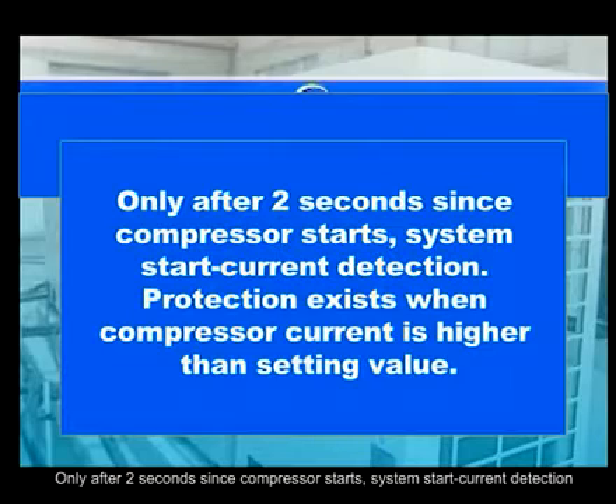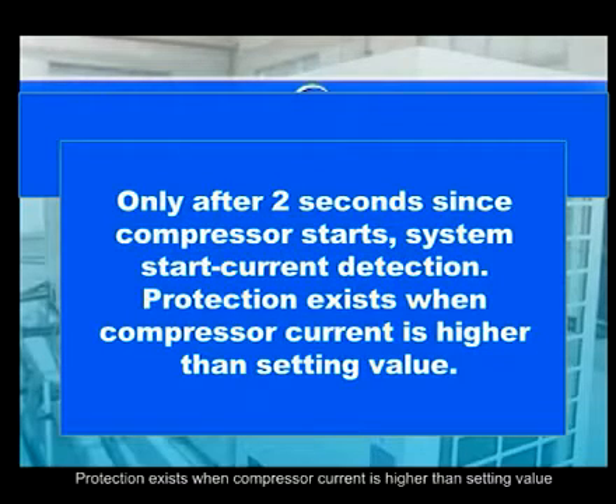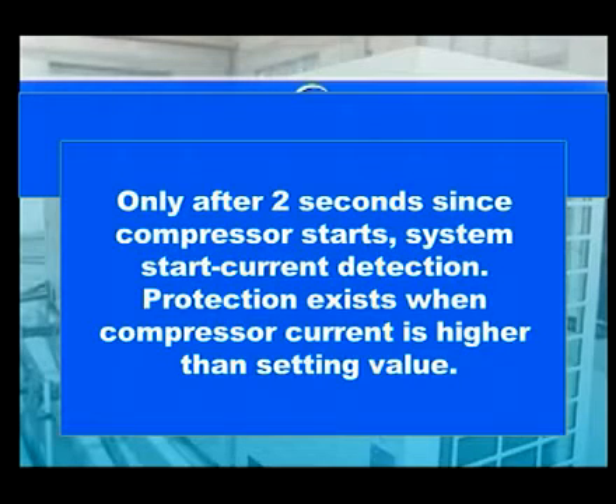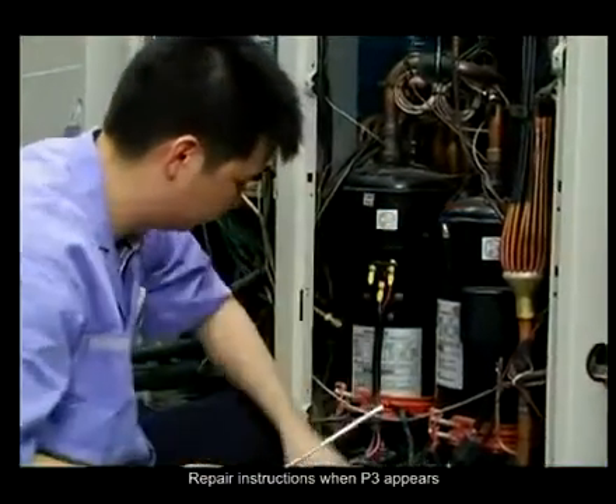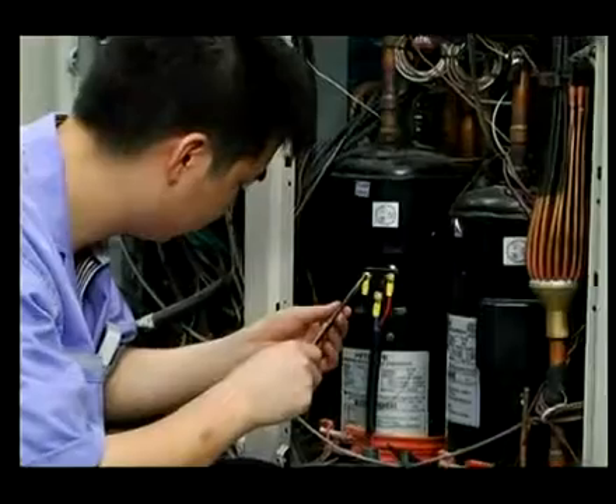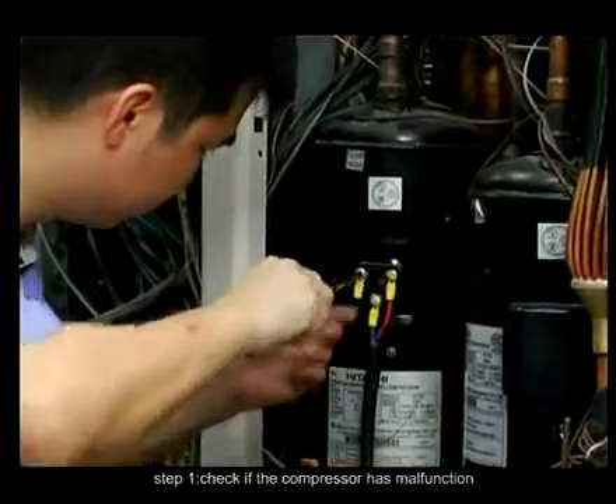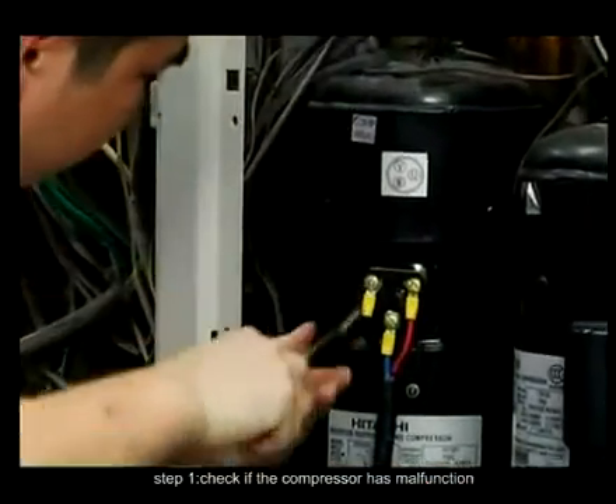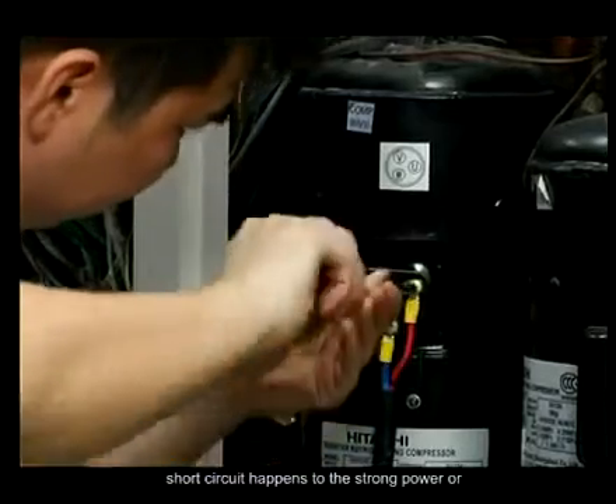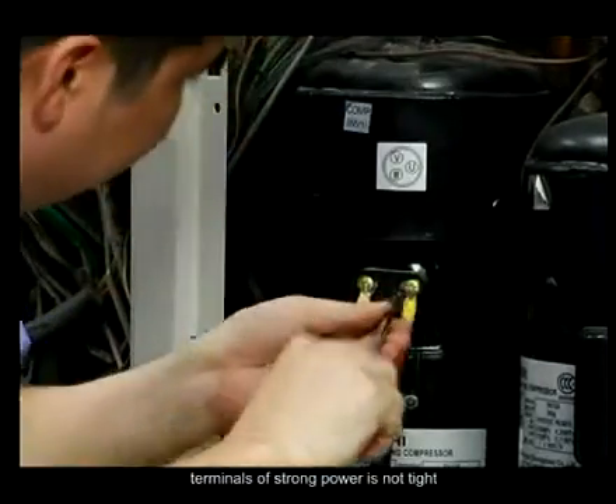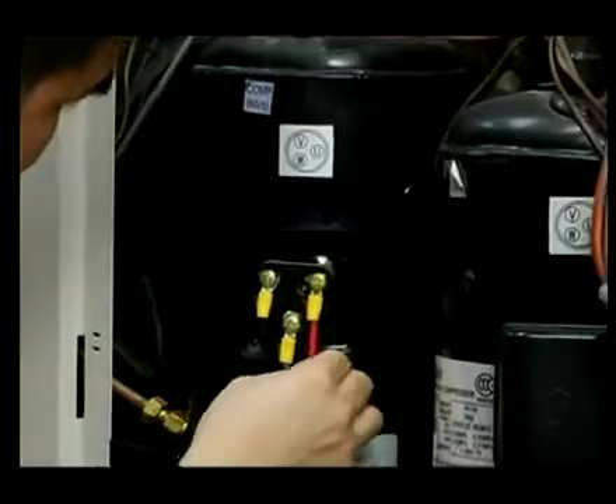Only after 2 seconds since the compressor starts, the system starts current detection. Protection exists when the compressor current is higher than the setting value. Repair instructions when P3 appears. Step 1. Check if the compressor has a malfunction, a short circuit happens to the strong power, or the terminals of strong power are not tight.